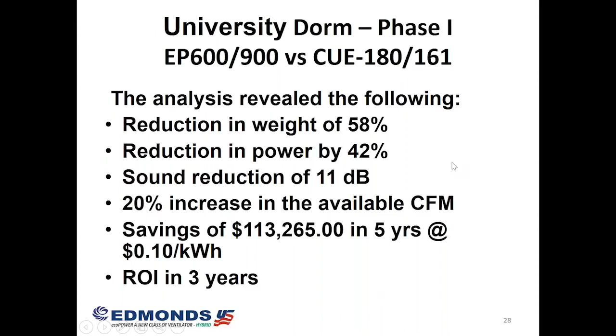The analysis showed a reduction in weight of 58%, a reduction of operating power by 42%, sound reduction of 11 dB, a 20% increase in the amount of CFM available, and energy savings of $113,265 over a 5-year period at 10 cents per kilowatt hour. These savings generated a 3-year ROI.